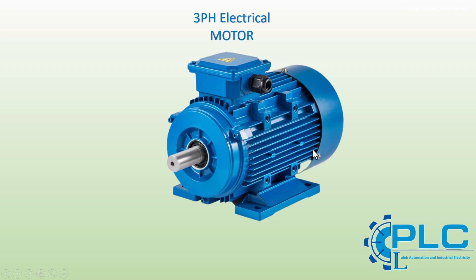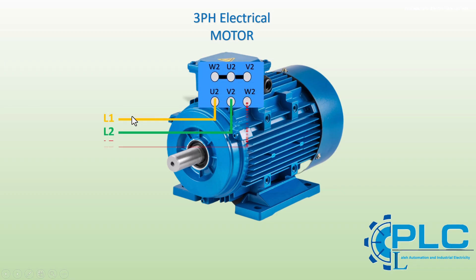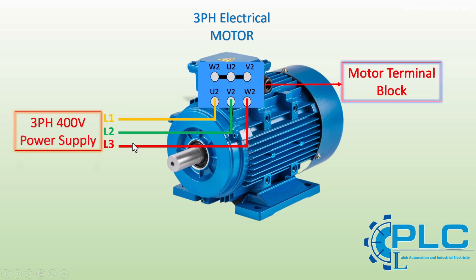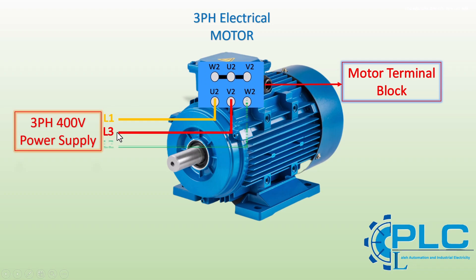A three-phase motor runs by receiving power through three separate wires, called phases. The direction of the motor's rotation depends on the order in which these phases are connected. To reverse the motor's direction, we simply swap two of the three-phase wires. This changes the sequence of the electrical current flowing through the motor, causing it to rotate in the opposite direction.